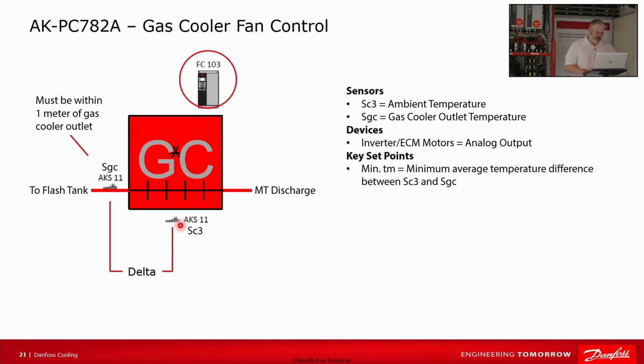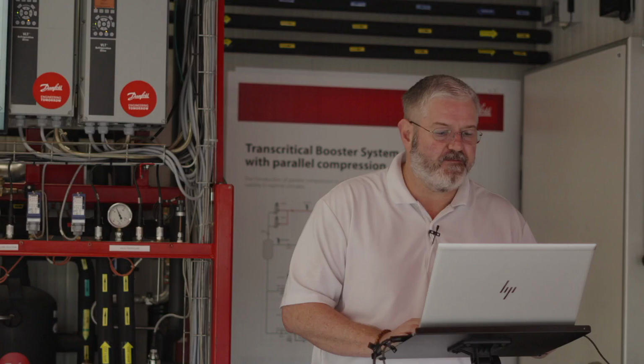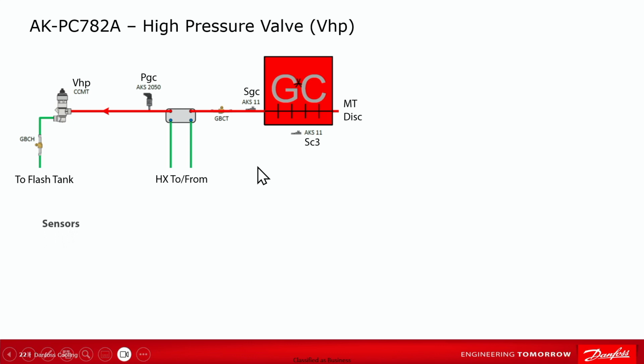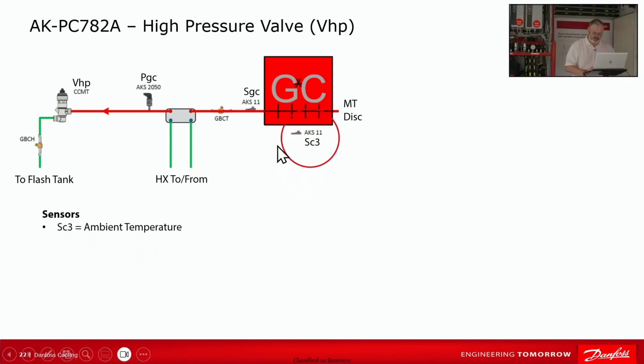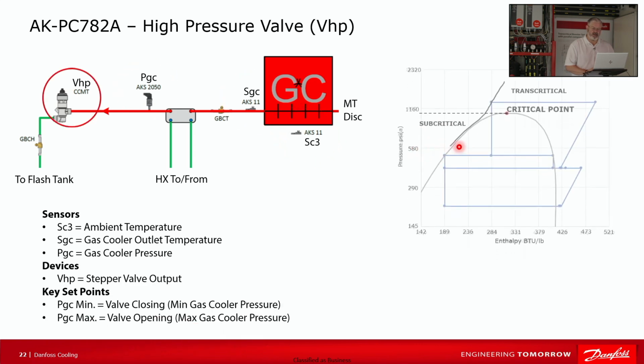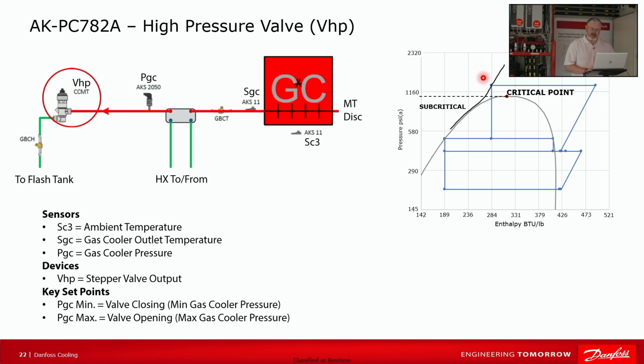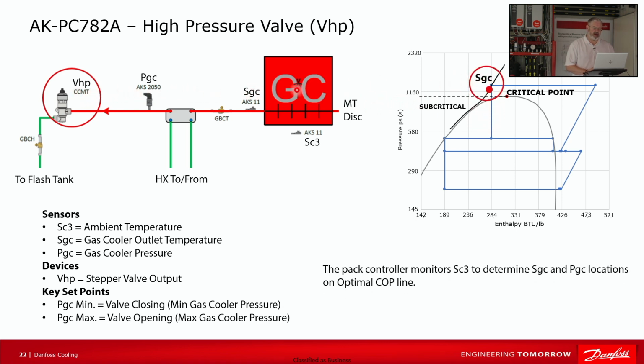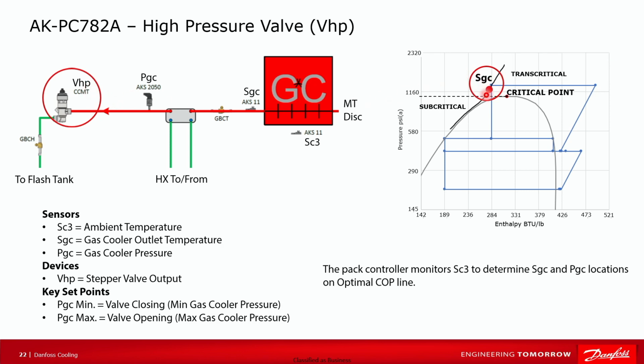On the high pressure valve side of that, if I can back up here, if we look back at how it controls, it doesn't really care about the delta between these two. One moment. My apologies for the awkwardness on your screens. So if we look back at the high pressure valve, remember the gas cooler fans, all they care about is the difference between these two. And then the high pressure valve, all it's really trying to do is make this temperature land on our maximum COP line that we saw earlier. So they are connected in the sense that what the fans are doing has an impact on the outlet temp from the gas cooler, but they don't necessarily fight each other. The high pressure valve would react as this moves to try and bring it back to that line. So there's never a chatter, which I think might have been the intent of the question. Hope that answers the question.